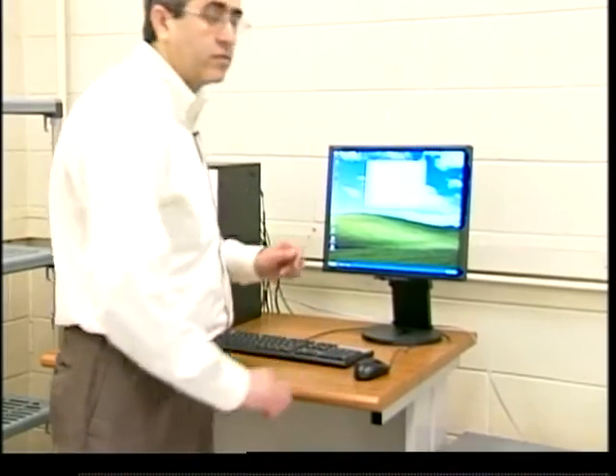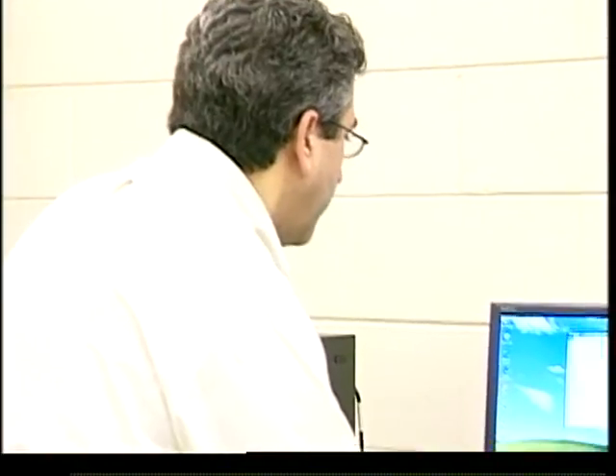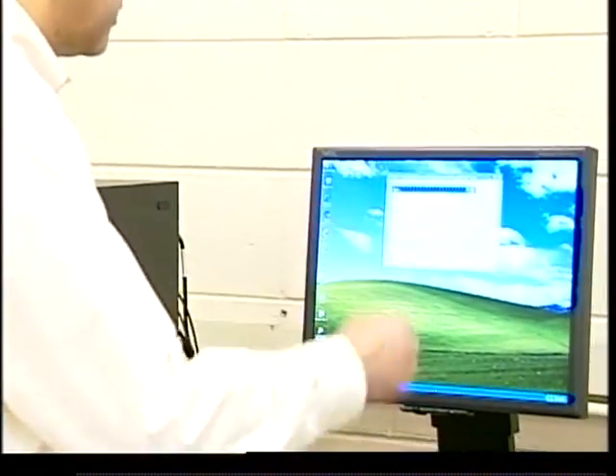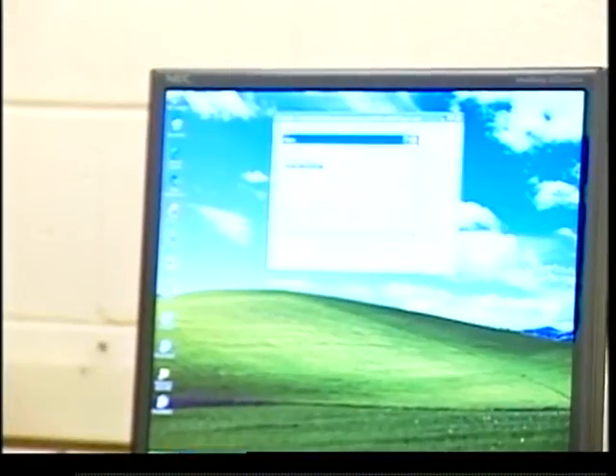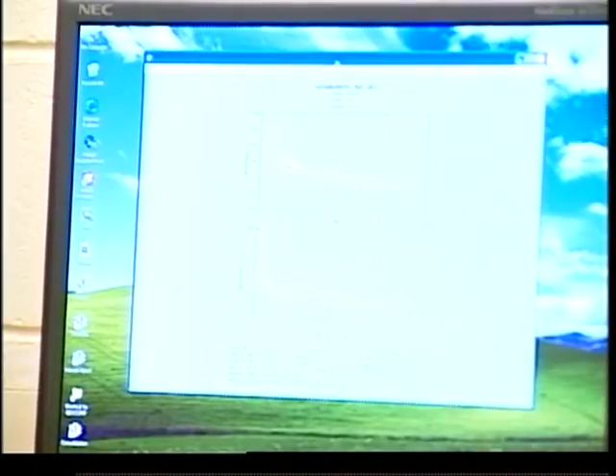Now what you need to do to look at the results is to go to file. You cannot go to report. So there's one step before that. You go to file, and you're going to load or reload the same test that we ran, and you open it. Now you have refreshed all the information on the screen. Then you go to report, graph, and you're going to see your time curves for the 13 steps. And you scroll through all these steps here. Make sure that everything is okay.